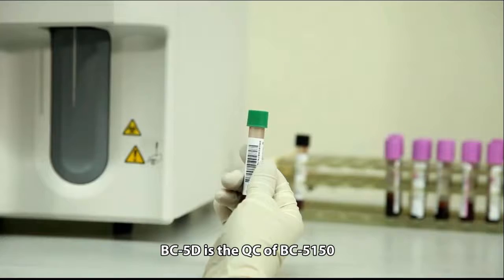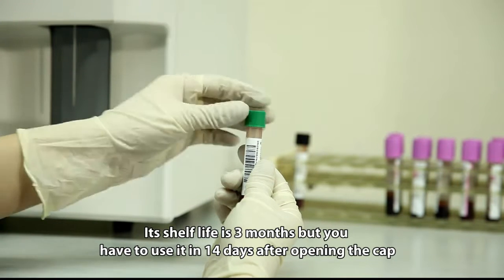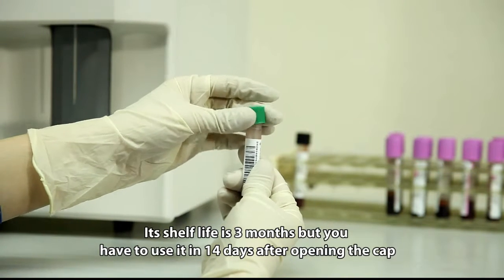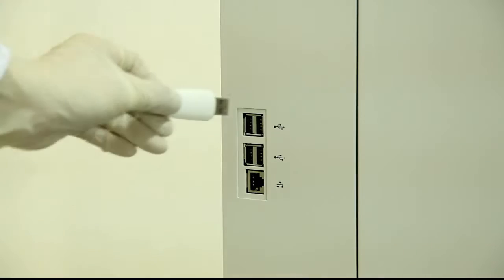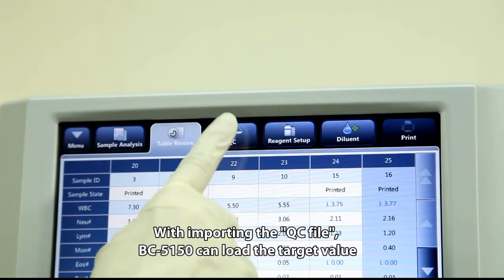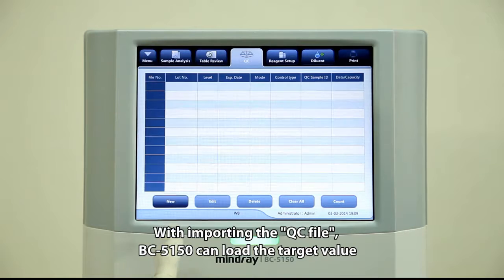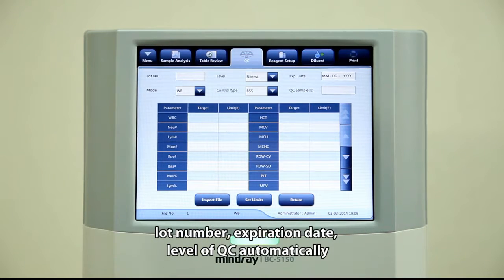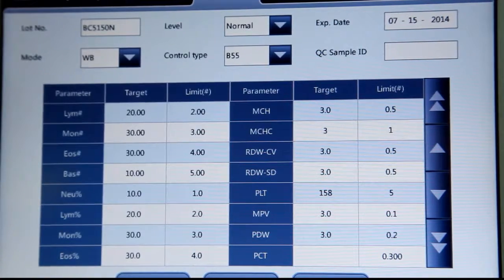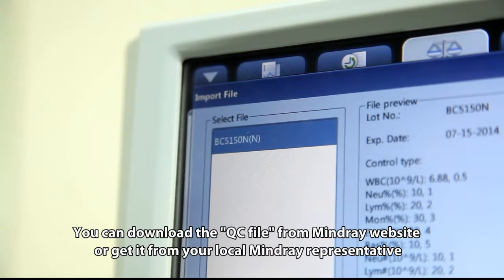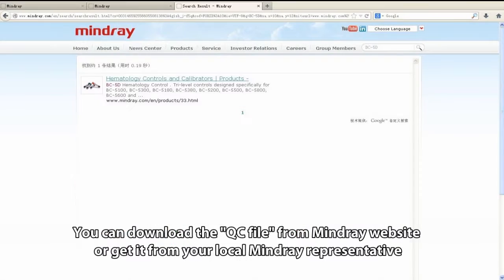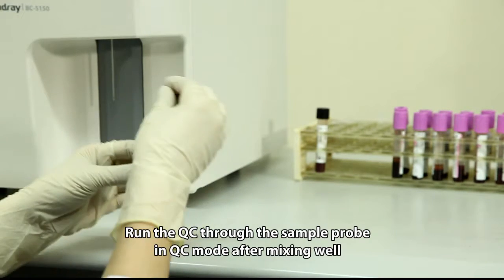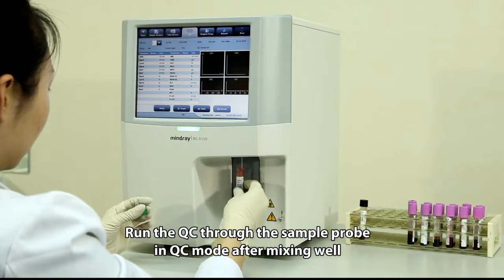BC-5D is the QC of BC5150. Its shelf life is 3 months, but you have to use it within 14 days after opening the cap. By importing the QC file, BC5150 can load the target value, lot number, expiration date, and level of QC automatically. You can download the QC file from the Mindray website or get it from your local Mindray representative. Run the QC through the sample probe in QC mode after mixing well.